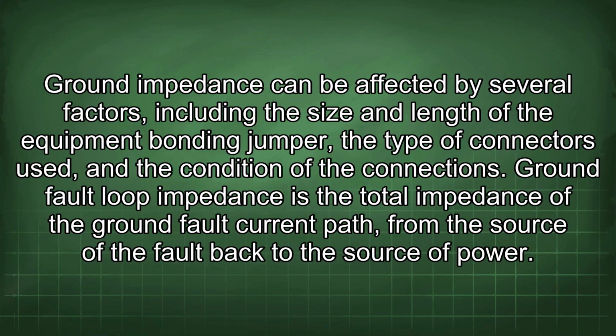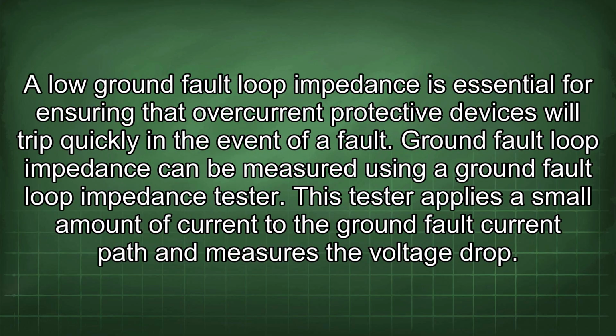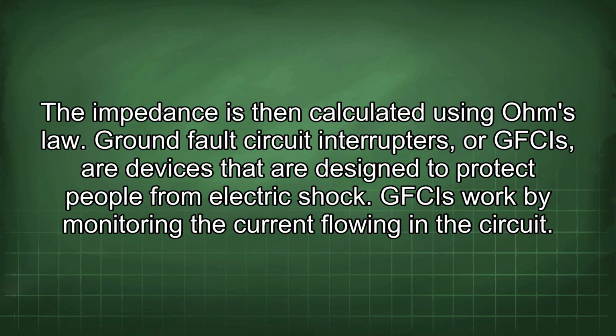Ground fault loop impedance is the total impedance of the ground fault current path from the source of the fault back to the source of power. A low ground fault loop impedance is essential for ensuring that overcurrent protective devices will trip quickly in the event of a fault. Ground fault loop impedance can be measured using a ground fault loop impedance tester. This tester applies a small amount of current to the ground fault current path and measures the voltage drop. The impedance is then calculated using Ohm's law.